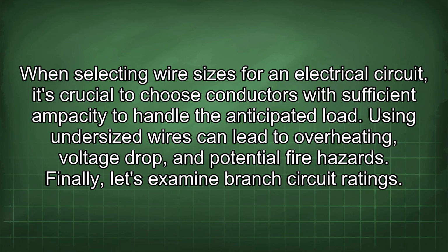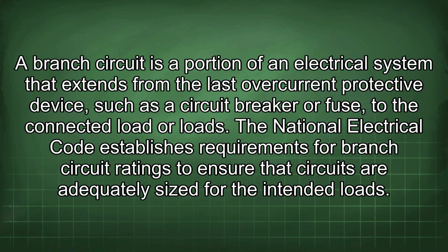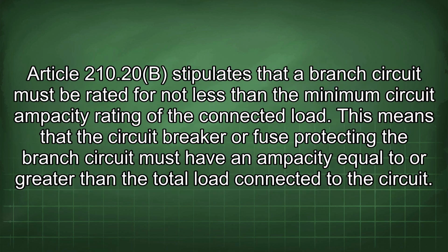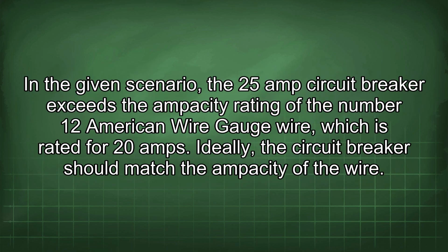Finally, let's examine branch circuit ratings. A branch circuit is a portion of an electrical system that extends from the last overcurrent protective device, such as a circuit breaker or fuse, to the connected load or loads. The National Electrical Code establishes requirements for branch circuit ratings to ensure that circuits are adequately sized for the intended loads. Article 210.20(B) stipulates that a branch circuit must be rated for not less than the minimum circuit ampacity rating of the connected load. This means that the circuit breaker or fuse protecting the branch circuit must have an ampacity equal to or greater than the total load connected to the circuit. In a given scenario, the 25 amp circuit breaker exceeds the ampacity rating of the number 12 American wire gauge wire, which is rated for 20 amps. Ideally, the circuit breaker should match the ampacity of the wire.